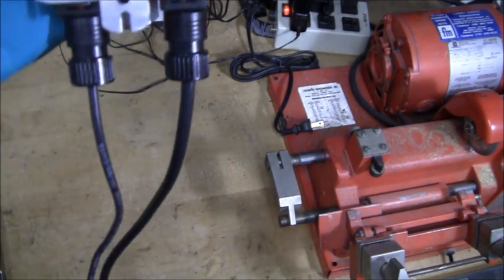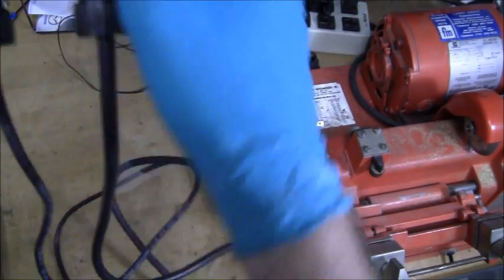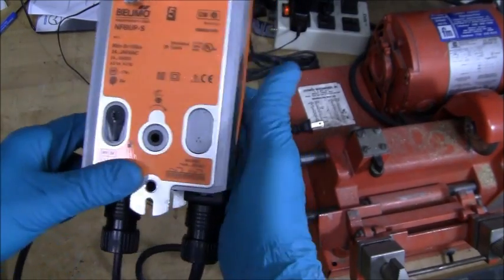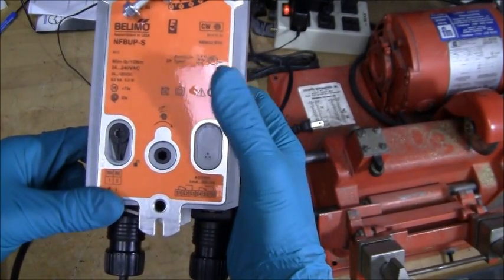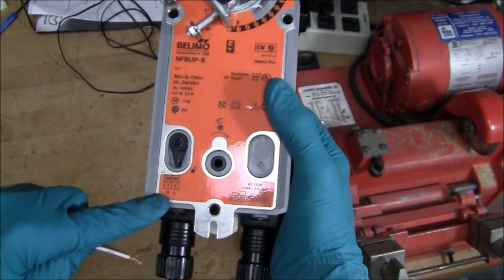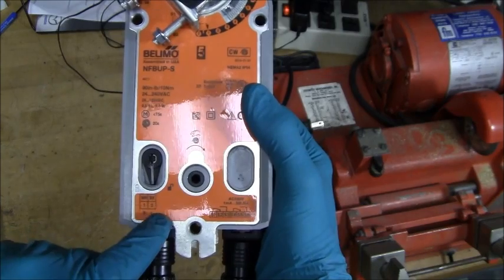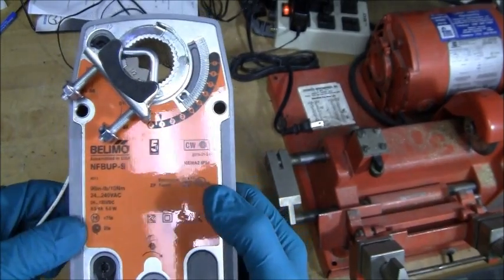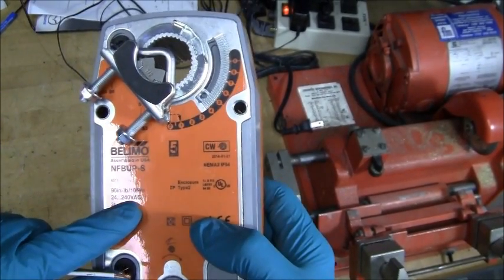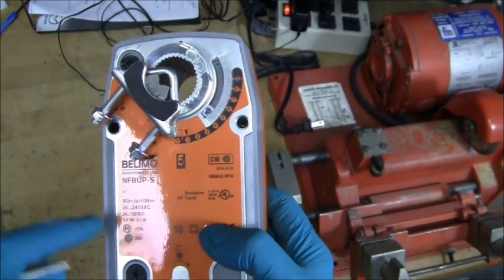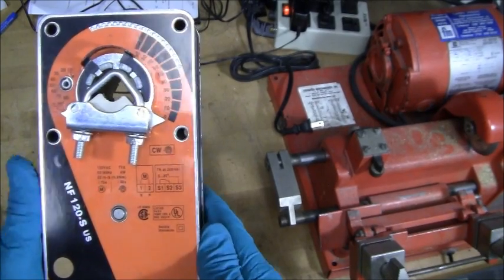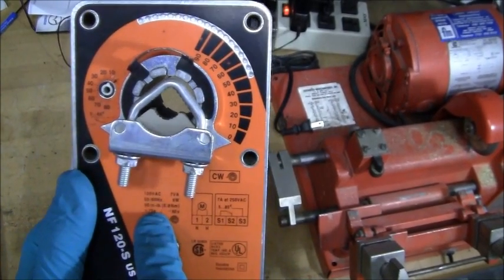Just like the other one, it's got two leads coming out. One of the leads only has two lines, a black and a white. That's my motor. The schematic is slightly different, but white is one, black is two, neutral and line voltage. The line voltage on this can take from 24 up to 240 volts. We're going to be using it for 120 volts here and in the field. The one we pulled out is rated at 120 volts.